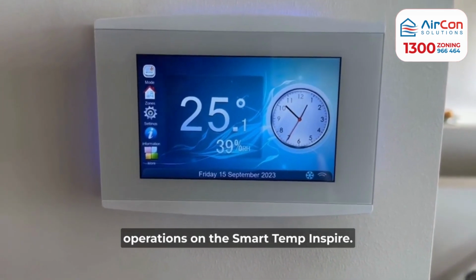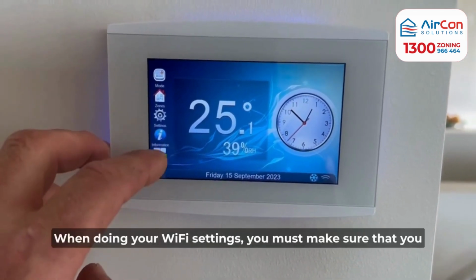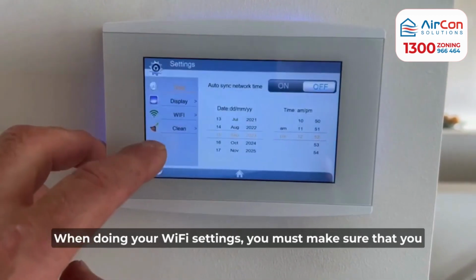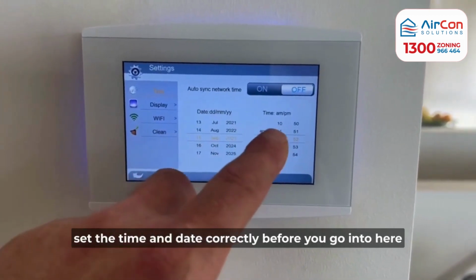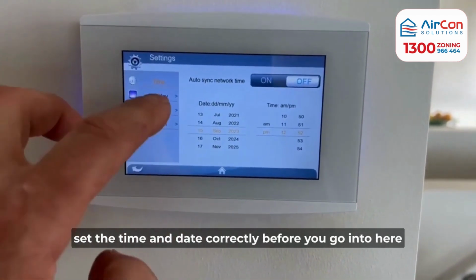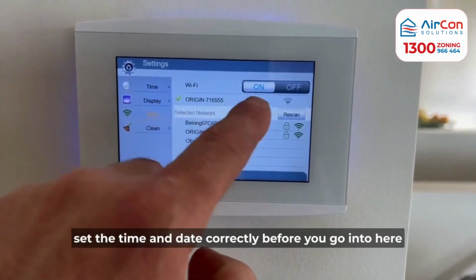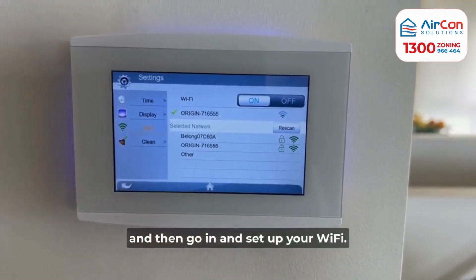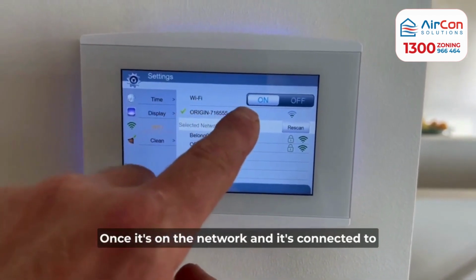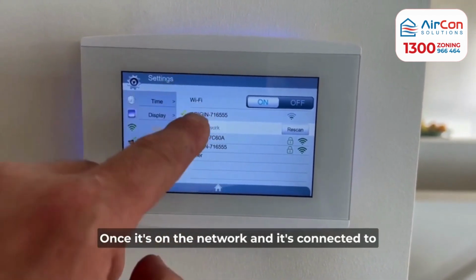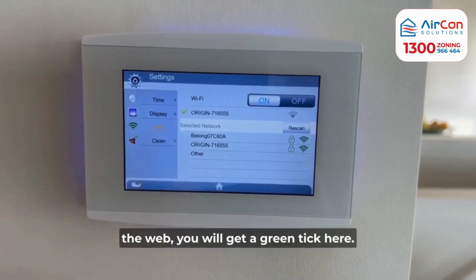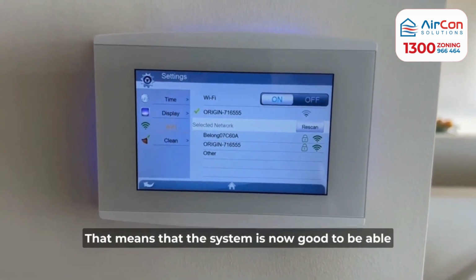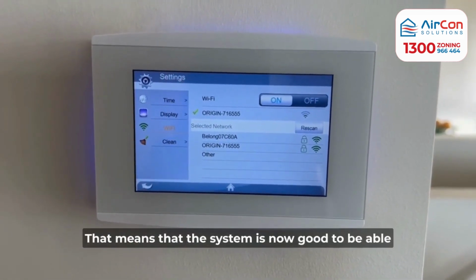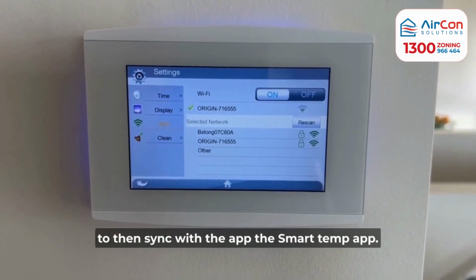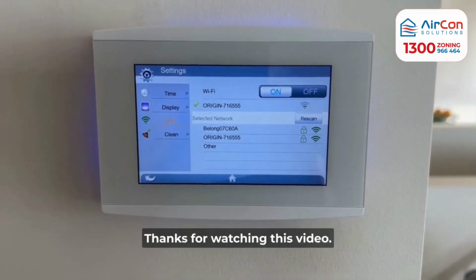the Smart Temp Inspire. Another tip too, when doing your Wi-Fi settings, you must make sure that you set the time and date correctly before you go into here, and then go in and set up your Wi-Fi. Once it's on the network and it's connected to the web, you will get a green tick here. That's when it means that the system is now good to be able to then sync with the app, the Smart Temp app.